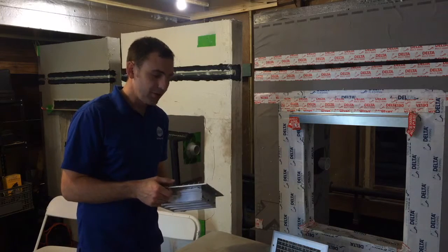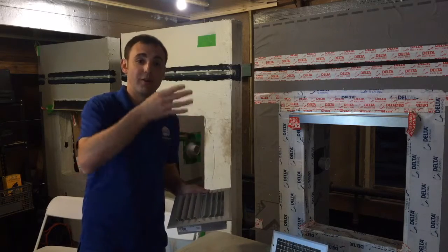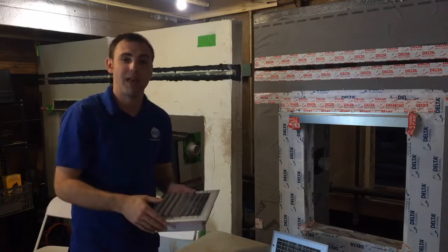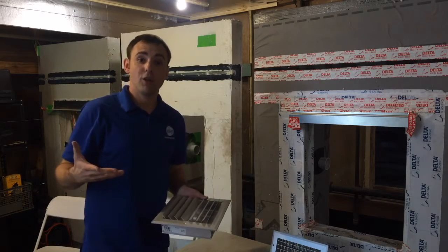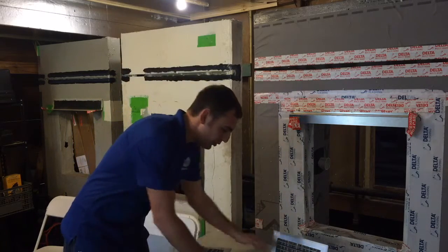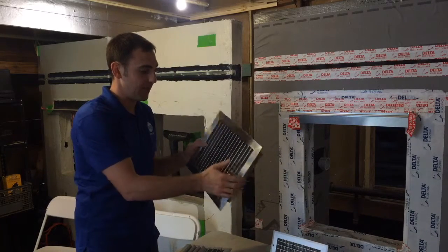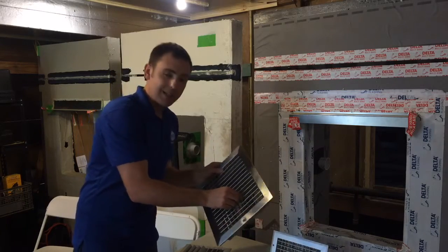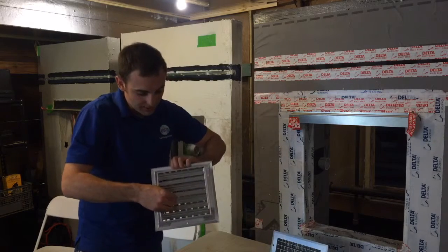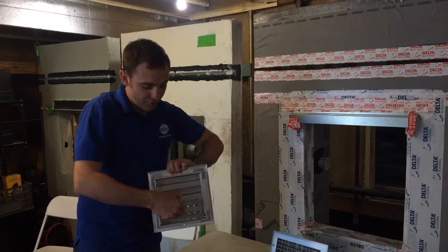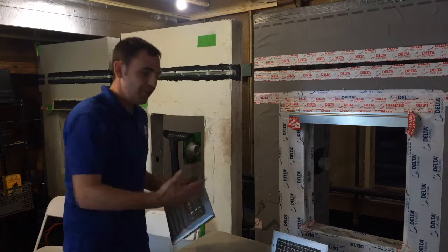So when we're talking about a grill, it's literally basically just sheet metal that's been pressed out, where there's one flat fin coming out that directs air in that way. It's a very simple way of looking at how air is going to get into the space. Then a register is going to be able to direct the air a little bit into its own path, wherever that may be. But the thing that it lacks is what the diffuser has. And the diffuser can diffuse the air on the back side. You can see these fins here closing, not letting air through as readily as when it is open. So all of those 3 things do things a little bit differently.